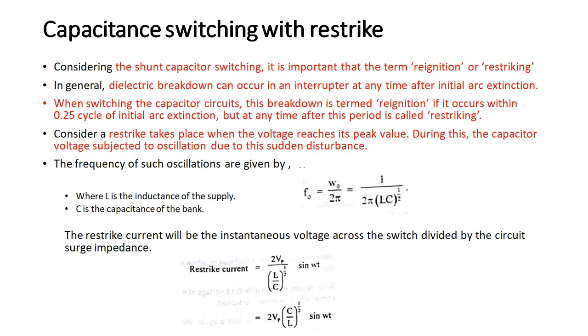Consider that restriking takes place when the voltage reaches its peak value, with the capacitor voltage subjected to oscillation due to sudden disturbances. The frequency of oscillation is given by F0 equal to W0 divided by 2 pi, that is, 1 by 2 pi root of LC. The restrike current will be the instantaneous voltage across the switch divided by the surge impedance. Restriking current is equal to 2 Vm divided by root of L by C, sin omega t.